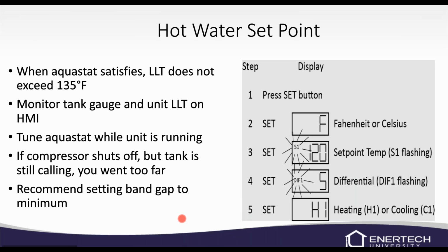Basically, when we set that aquastat, we're going to want to set it where the aquastat satisfies, but the leaving load temperature does not exceed 135. These tank sensors or aquastats, I've seen them be off by quite a bit straight out of the box. So I don't really rely so much on what the temperature of the aquastat is, but I just want to make sure that we're not going above 135 leaving the unit when the tank satisfies.